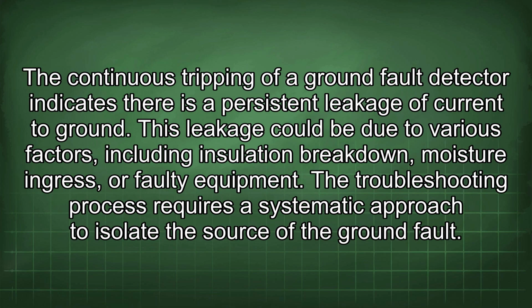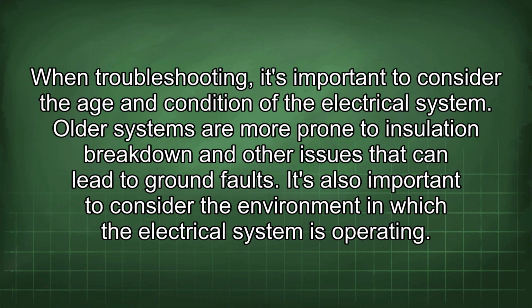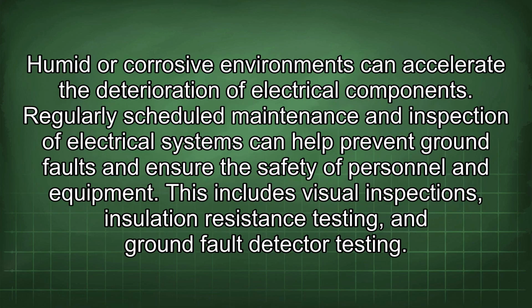The continuous tripping of a ground fault detector indicates there is a persistent leakage of current to ground. This leakage could be due to various factors, including insulation breakdown, moisture ingress, or faulty equipment. The troubleshooting process requires a systematic approach to isolate the source of the ground fault. When troubleshooting, it's important to consider the age and condition of the electrical system. Older systems are more prone to insulation breakdown and other issues that can lead to ground faults. It's also important to consider the environment in which the electrical system is operating. Humid or corrosive environments can accelerate the deterioration of electrical components.